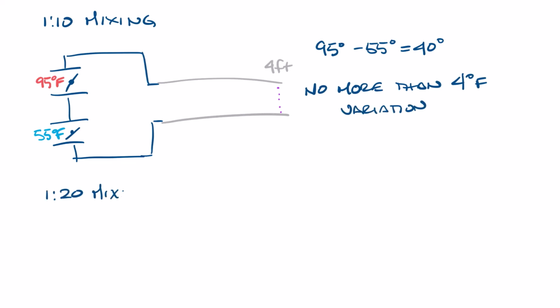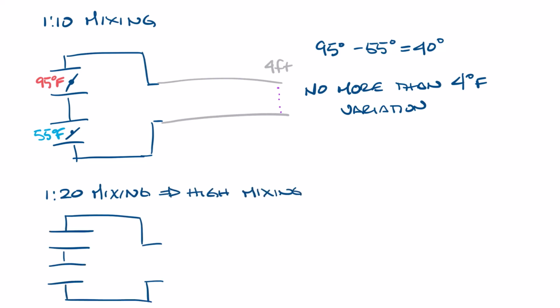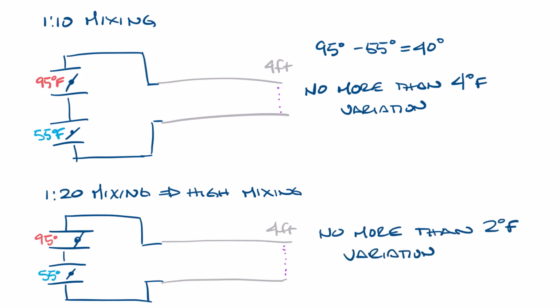A high mixing box is considered 1:20 mixing. So again, let's draw a box in and let's have 55 degree cold air and 95 degree hot air again, and 4 feet of ductwork. Again, our cold air is 55 degrees and our hot air is 95 degrees. This is still a 40 degrees difference, but now 1:20 mixing means that we have no more than 1 degree of variation per 20 degrees differential. So if we took a traverse of temperature readings at 4 feet from the discharge, we'd have no more than 2 degrees variation in that temperature.